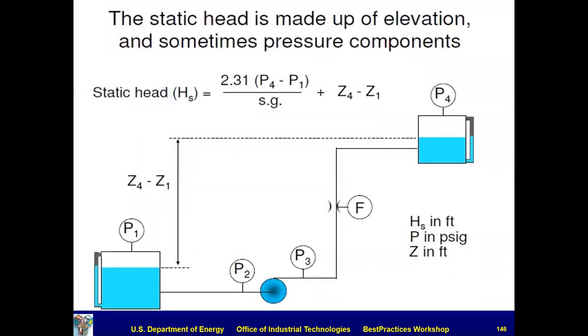Okay, so here's a little equation. We're assuming that we would measure these pressures in PSIG, which is pretty common in the US. So that delta P, P4 minus P1, times 2.31 converts standard water from PSIG to feet of head. And if your specific gravity is not 1, you can still use the 2.31, but you divide by specific gravity. And that will produce the feet of static head.